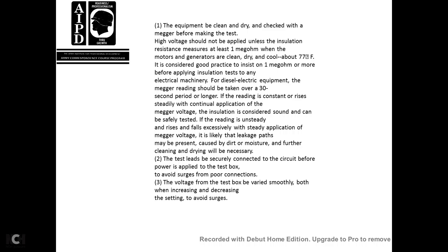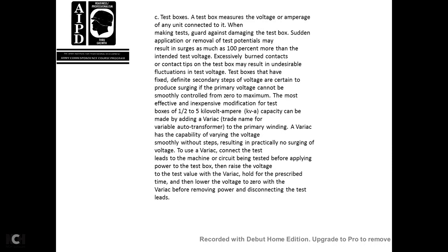can be safely tested. If the reading is unsteady and rises and falls with a steady application of the measured voltage, it usually indicates leakage, and the leakage path may be caused by dirt and moisture. Further cleaning and drying will be necessary. The test leads should be securely connected to the circuit before the power is applied to the test box. To avoid surges with the power connected, the voltage from the test box may be varied smoothly, both when increasing and decreasing the setting, to avoid surges.